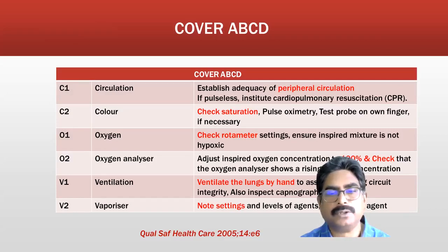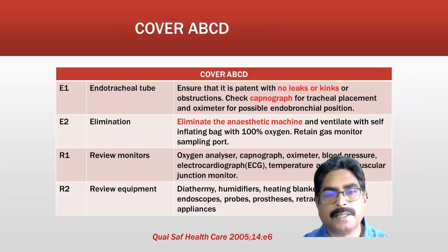Vaporizer, note the settings and the level of the agents. Remember, leaks are more common in the low pressure system, that is in the vaporizer. So you check the vaporizer.